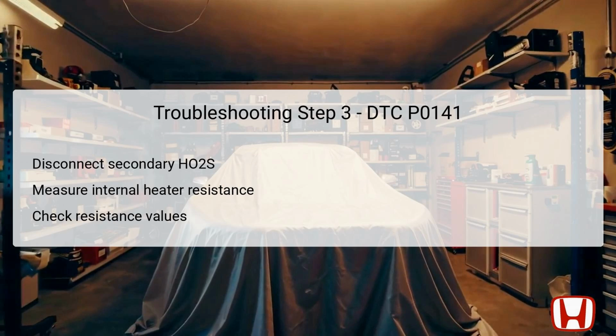The expected resistance value should fall between 5.4 to 7.3 ohms at room temperature. If the resistance is within this range, it indicates that the heater is functioning correctly, allowing you to move on to the next troubleshooting step.